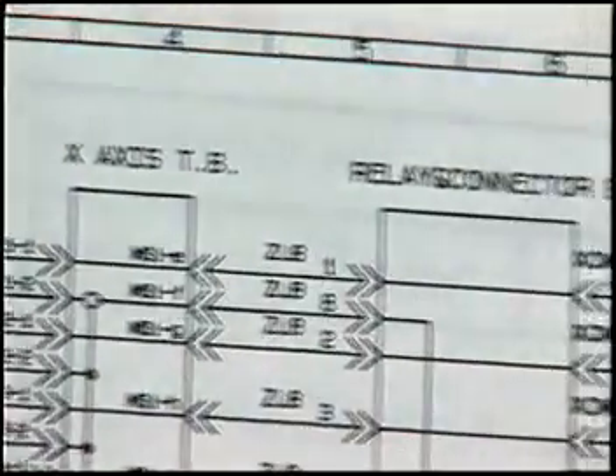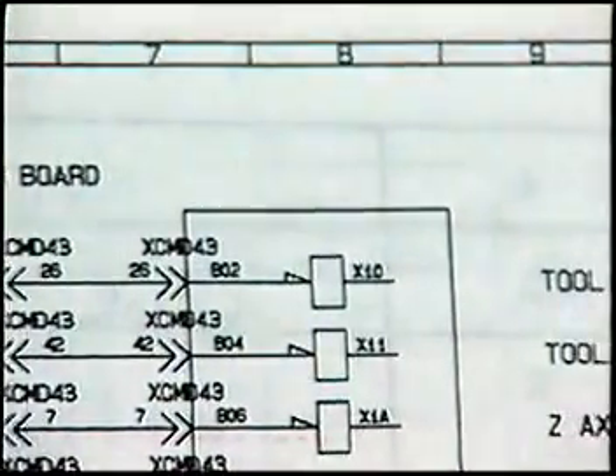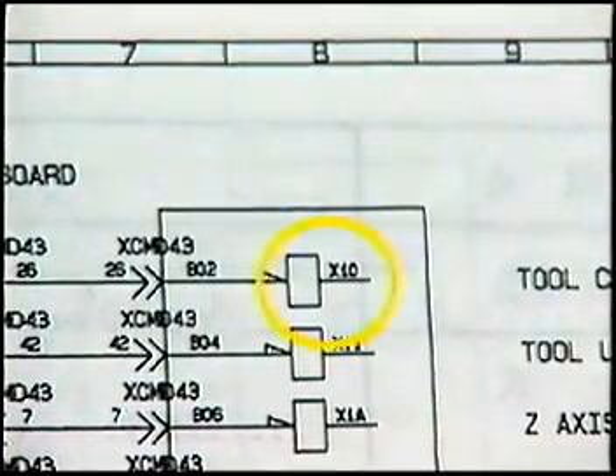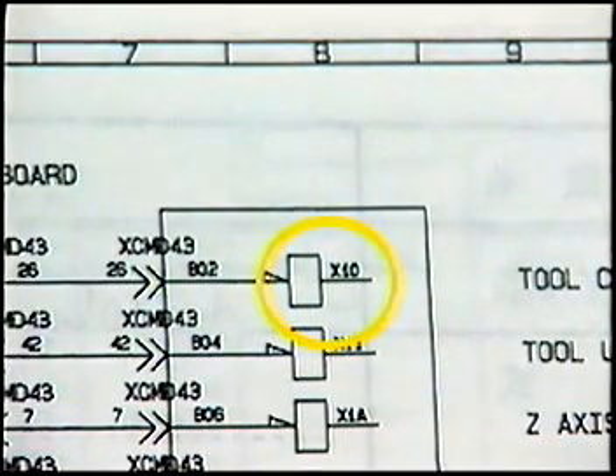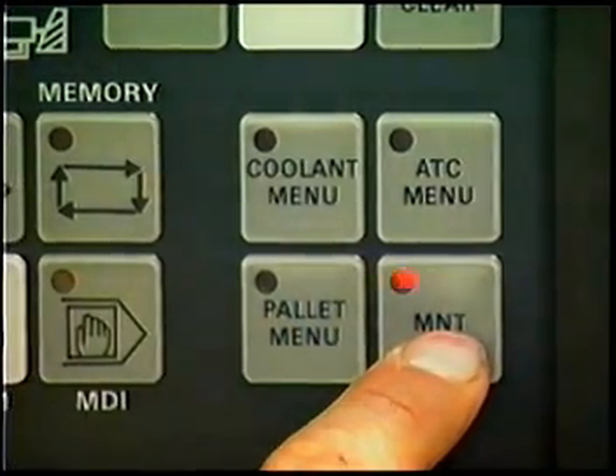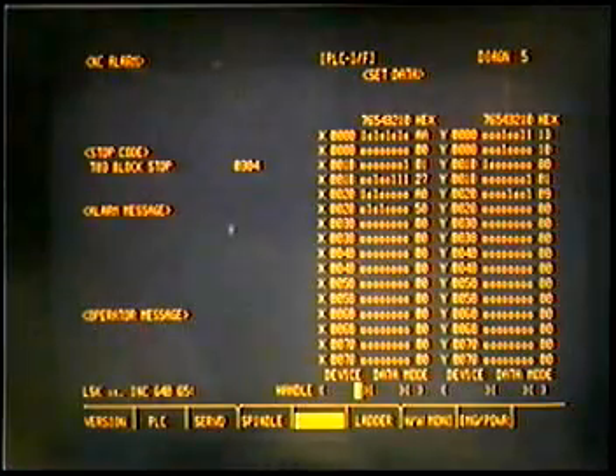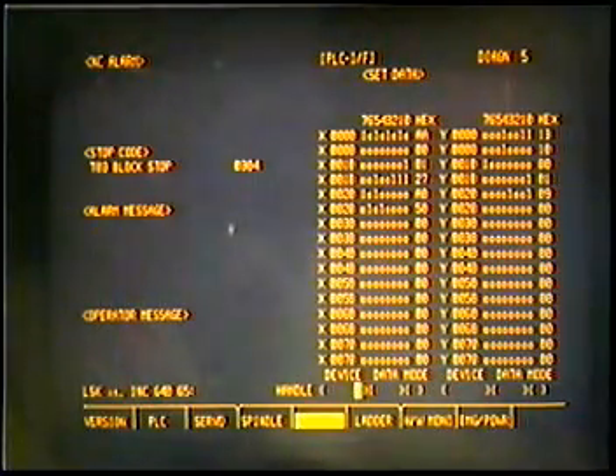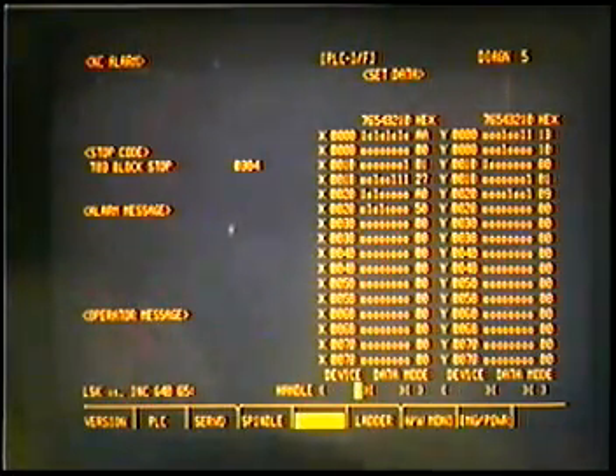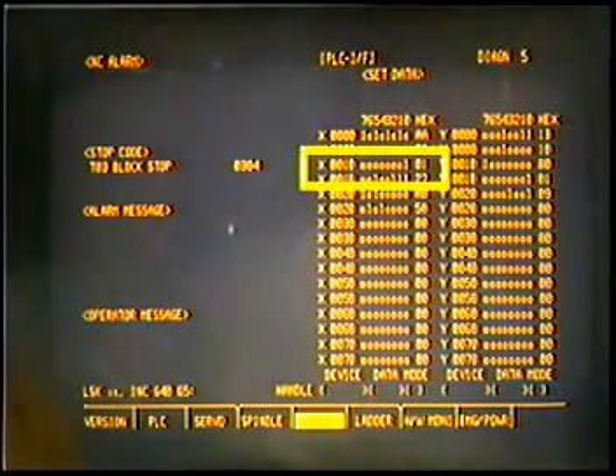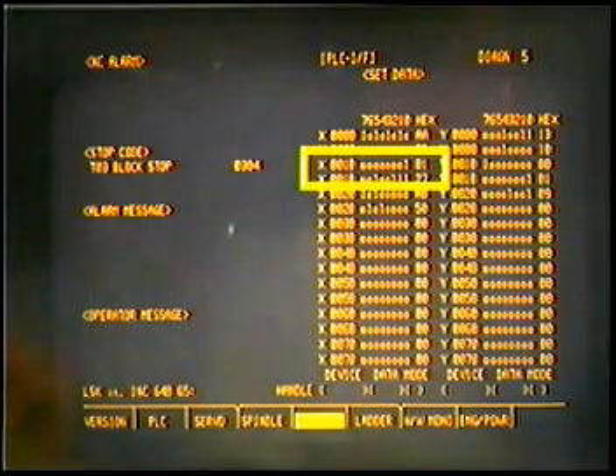Shown on the right of the sample page is the diagnostic addresses where the inputs can be monitored. Looking at the address X10, we can see that this is the input for the tool clamp proximity switch. Pressing the MNT button on the lower right-hand corner of the M32B control will access the diagnostic addresses. To look at an address, you will need to know what line will contain the address you need. For our example, X10 is located in line X0010, far right-hand bit.